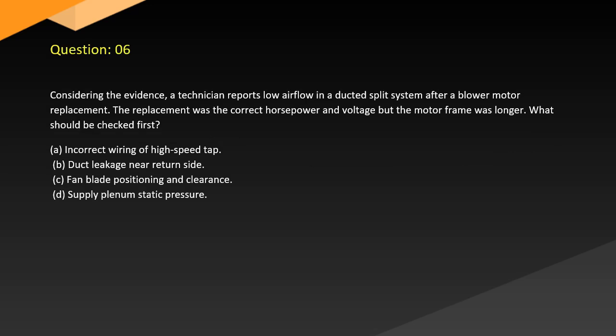Question 6. Considering the evidence, a technician reports low airflow in a ducted split system after blower motor replacement. The replacement was the correct horsepower and voltage, but the motor frame was longer. What should be checked first?